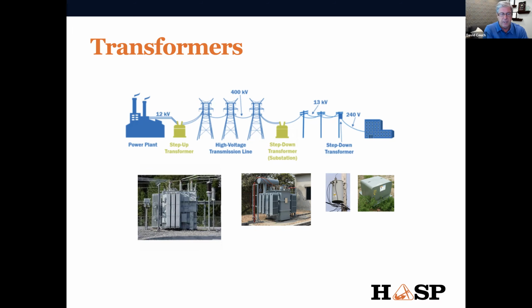You see that below the graphic. Once it gets to its destination where you want to work with it, you step it down to a lower voltage. The voltage on the poles around which we drive is typically, in Holland, either 12,000 or 7,000 volts. When it comes to your home, it goes through a final step-down transformer, which could be in the ground depending on the neighborhood and how the utility is delivered. If it's on a pole, there's a transformer that steps it down to 240/110 volts, or if it's in the ground, you'll see a transformer like that in your neighborhood. There might be anywhere from 3 to 5 homes on each transformer, depending on the size of the homes and the amount of energy they draw.